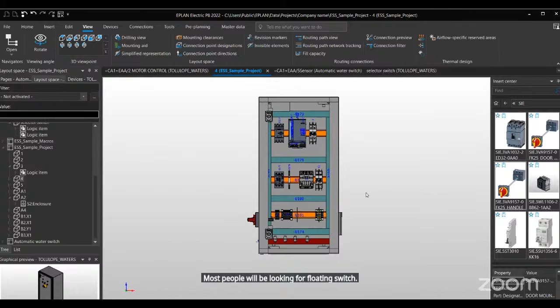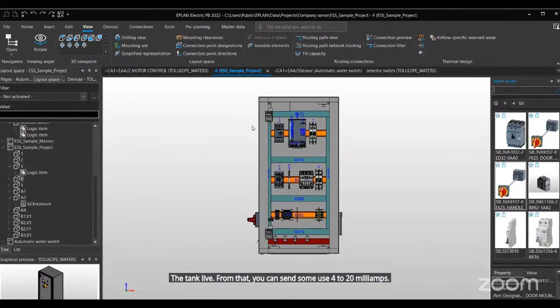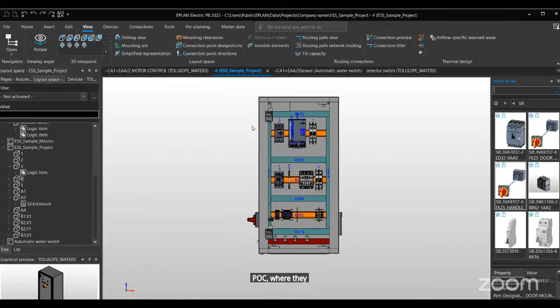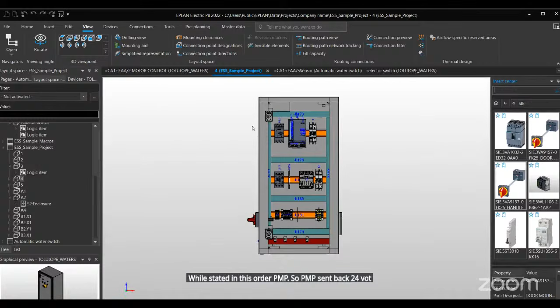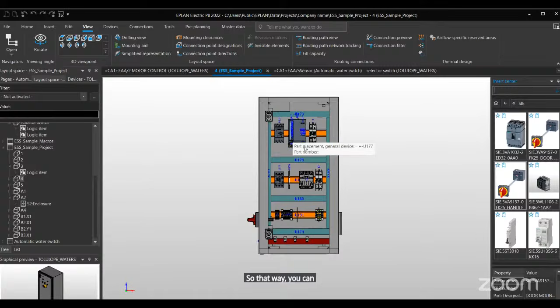So what the ultrasonic sensor does is you place it on top of the tank. It sends sound waves into the tank, and from the feedback of the sound wave, like how many waves return back, that's how it calculates the tank level. From that, you can send some signal, like 4 to 20 milliamps analog signal back to the PLC where they can calculate. But I stated in the sub that PNP, so PNP sends back 24 volts, just like a regular switch and sensor. That way you can build that.